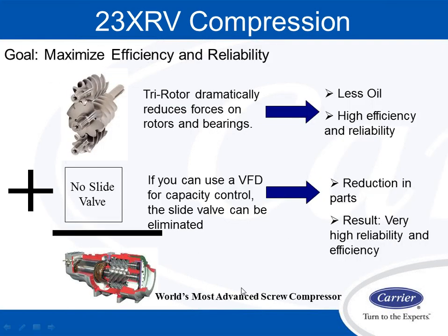So the goal was to maximize the efficiency and the reliability. Again, we have a tri-rotor. Because the forces cancel, we operate with as much oil as can fit in the palm of my hand. So less oil makes it more efficient. Now I have a larger surface area and discharge area on the screw. A larger discharge area in the screw means I can get more efficiency out of it. So it's higher efficiency, very few moving parts, so it's got high reliability. I eliminated the slide valve, and it operates with a VFD standard.